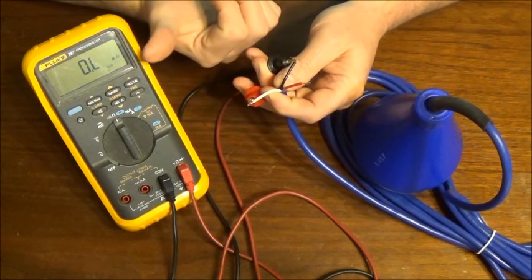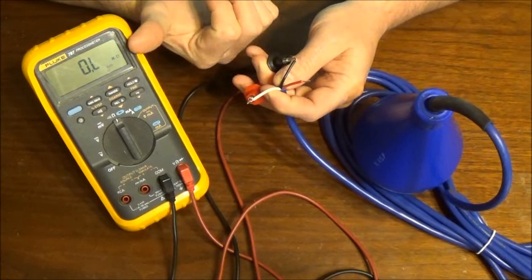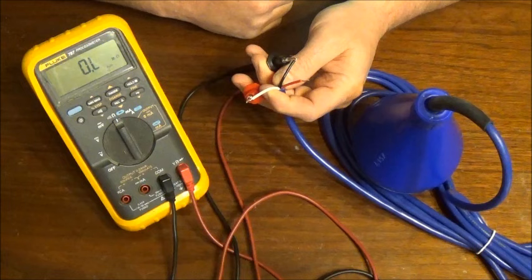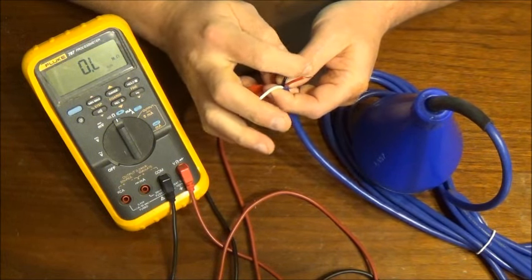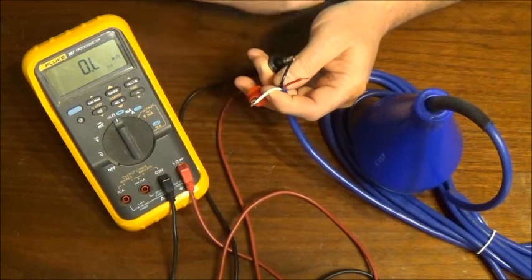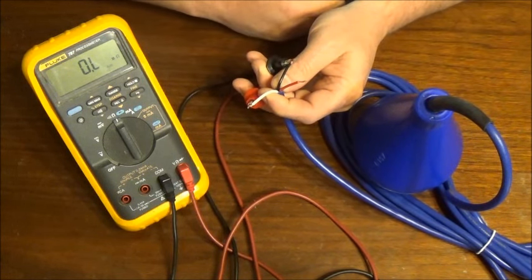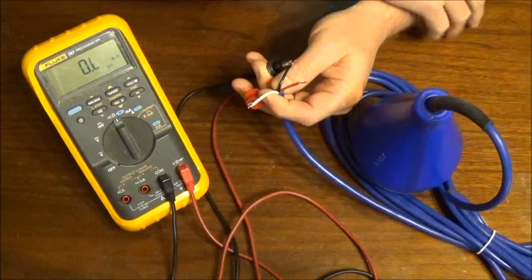You measure across those leads and you measure O.L.. That's fine if the float should be reading as normally open in the down position. So let's say that it is. Now we've got our leads measured across the float.